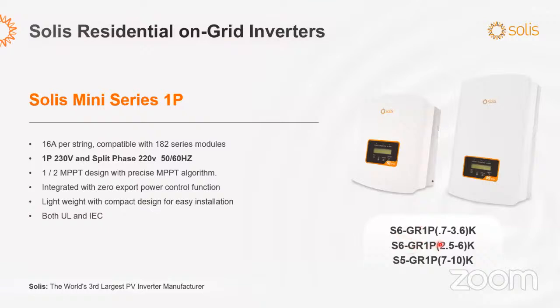It depends on the size of your PV installation and your requirements, so we offer flexibility in terms of design. These inverters can be used in single phase European configuration, which is 220 or 230 neutral to one phase, and also for split phase 220/240 in both frequencies, 50 and 60. This is a very common question we receive from the different islands, especially because they have all these different configurations and requirements, so we offer this flexibility with these products.